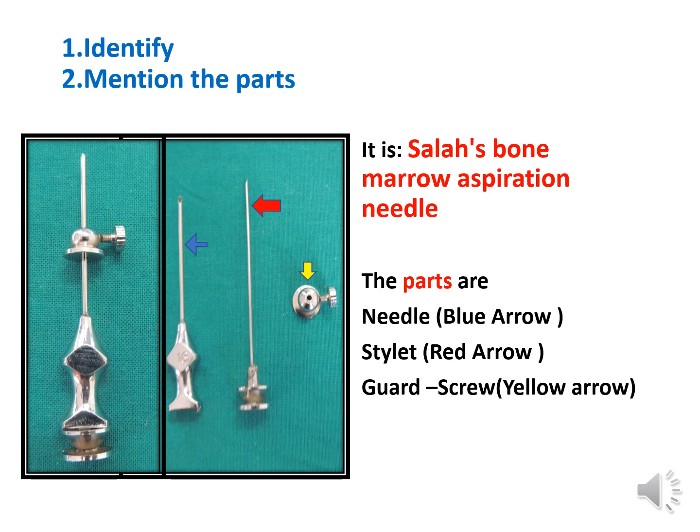The guard is to control the depth of insertion, how deep we are putting the needle in the bone. So you can control so that it doesn't go much deeper and harm the deeper organs.